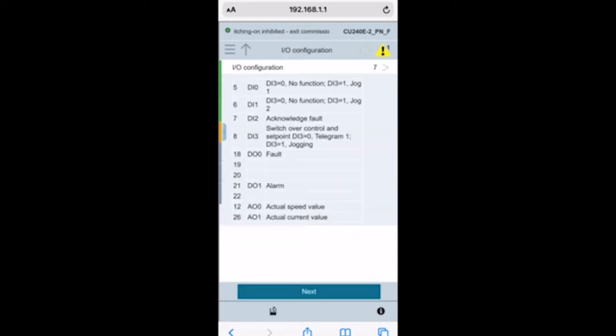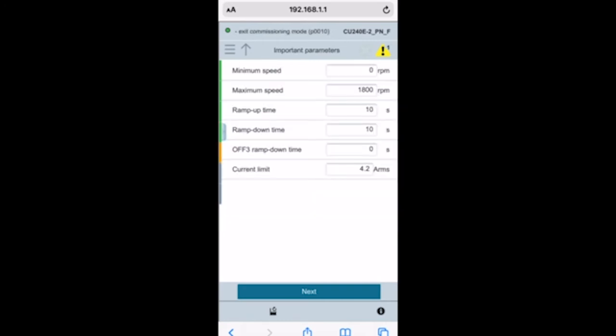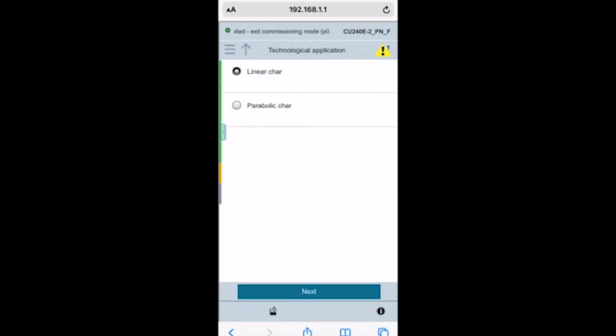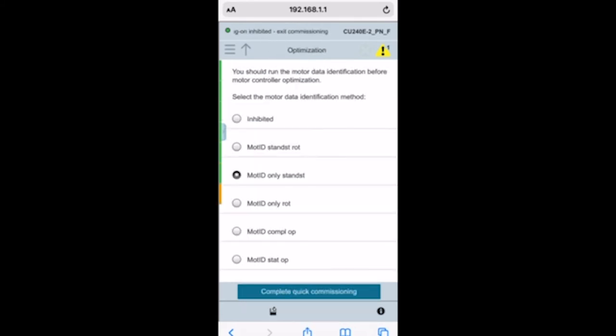Once I've typed in all that information, I'm going to hit next. Now it's going to ask you for your IO configuration. This is the standard configuration. You can make changes if you want. Now I'm going to enter in our minimum maximum speed. For this demo, I'm entering two seconds for ramp up and two seconds for ramp down time. Linear or parabolic, we're selecting linear.